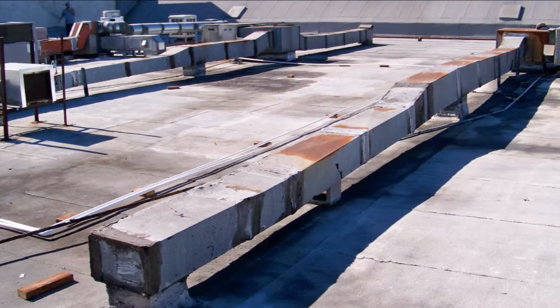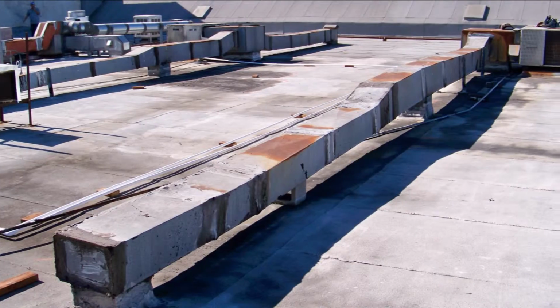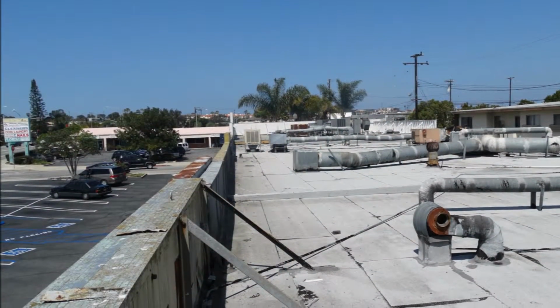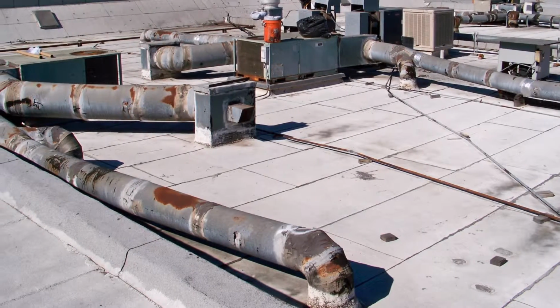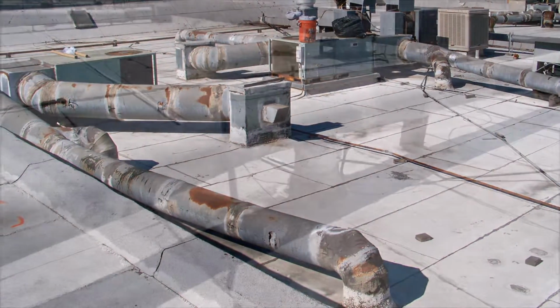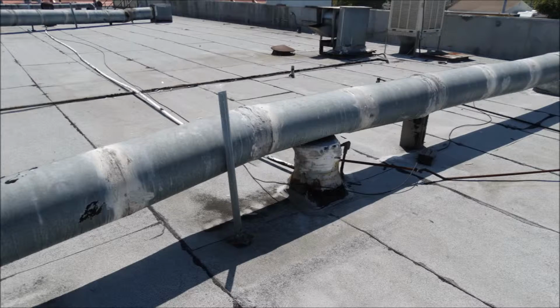Any water getting inside a duct will usually follow the duct's interior wall leading to the inside of the building. To an untrained eye, this will resemble a roof leak and is often assumed to be a roof issue rather than the aged-out or badly repaired ductwork causing it.